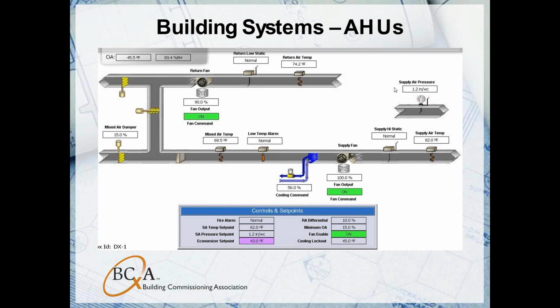These units have chilled water cooling only, no heat. So the way they handle that is they raise the supply air temperature set point and allow the electric reheats at the VAV boxes to handle any reheating that's needed. And they do have cooling only boxes, so they have to keep that discharge air temperature fairly high so you're not freezing people out. These units serve individual risers that feed medium pressure duct on floors 2 through 24. Each floor has a ring of ductwork that's fed from each air handler. So essentially these units are headered together at the floor level, which is important, and we'll discuss that a little later.